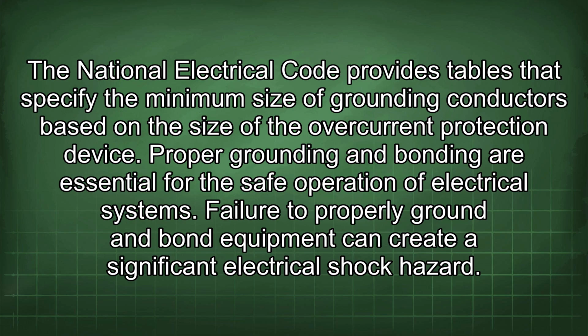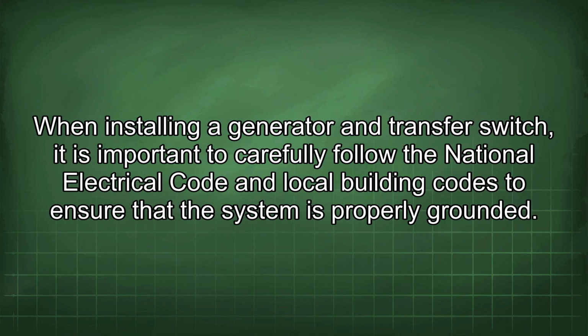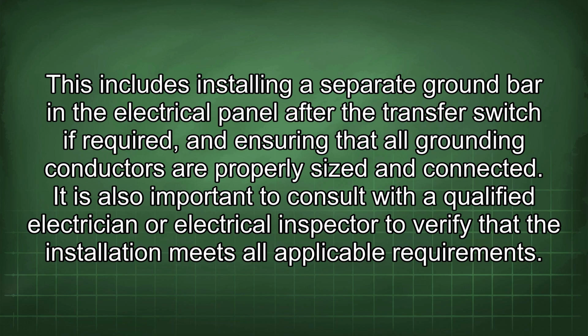Failure to properly ground and bond equipment can create a significant electrical shock hazard. When installing a generator and transfer switch, it is important to carefully follow the National Electrical Code and local building codes to ensure that the system is properly grounded. This includes installing a separate ground bar in the electrical panel after the transfer switch if required, and ensuring that all grounding conductors are properly sized and connected. It is also important to consult with a qualified electrician or electrical inspector to verify that the installation meets all applicable requirements.